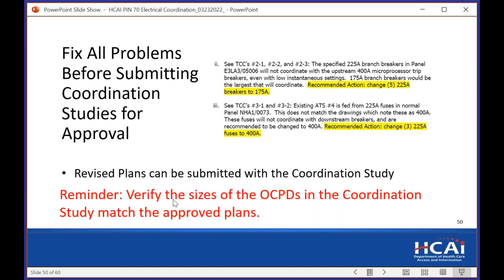One big problem that I see over and over again is that the breaker sizes and fuse sizes shown in your coordination study do not match the approved plans. We will compare your single line diagram in the approved plans and your panel schedules with the information shown in your coordination studies. So make sure they match.